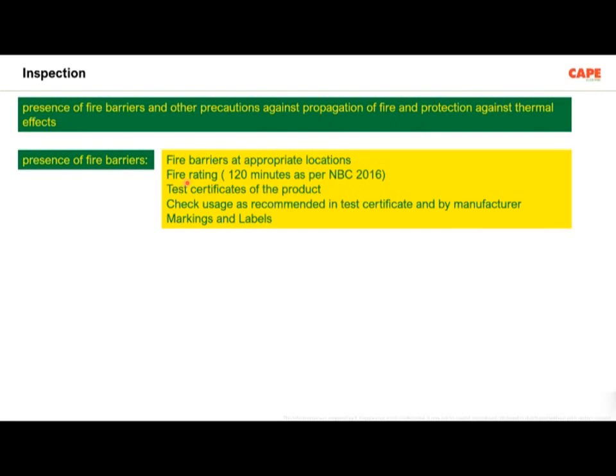Then he has to find out whether the ceiling material is able to handle 120 minutes as per the National Building Code, whether it is tested, check the usage as recommended in the test certificate and by the manufacturer, and whether the markings and labels are there. So it is the job of the inspector to ensure that all these 5 points are inspected and he is recording it in his report. As a result, 1 of the 3 requirements is handled.